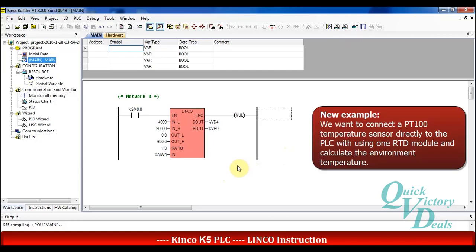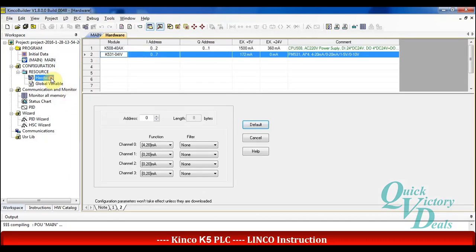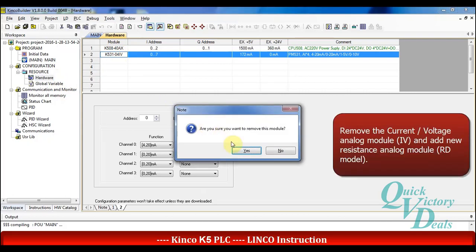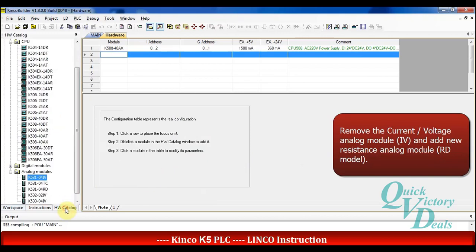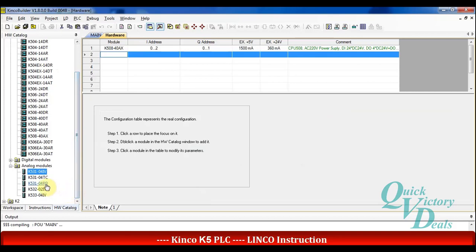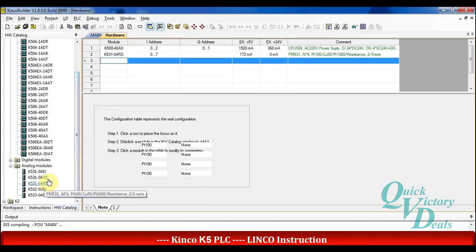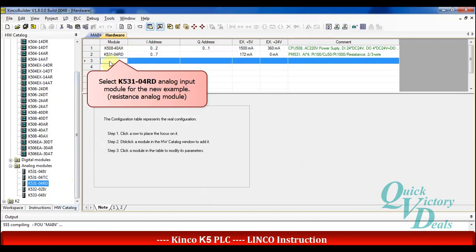This time we want to connect the PT100 sensor directly to the RTD module of the Kinco CPU to check the temperature of the environment. So we will go to change the hardware configuration. I will remove the previous module that supports voltage or current for analog input, and I will add another module that supports RTD sensors directly without any transmitter.